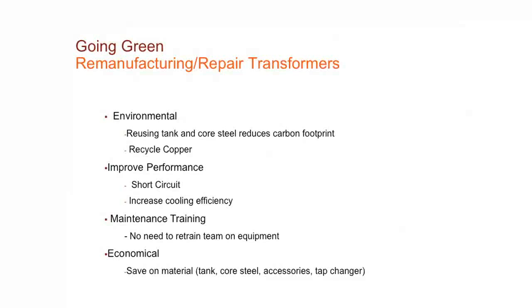When you're repairing a transformer or recycling some of the components, oftentimes, like I mentioned earlier, when you repair and reuse, redesign the windings, you can improve the short circuit strength. If you repair the cooling equipment or upgrade the cooling equipment, you can increase the cooling efficiency of the transformers.